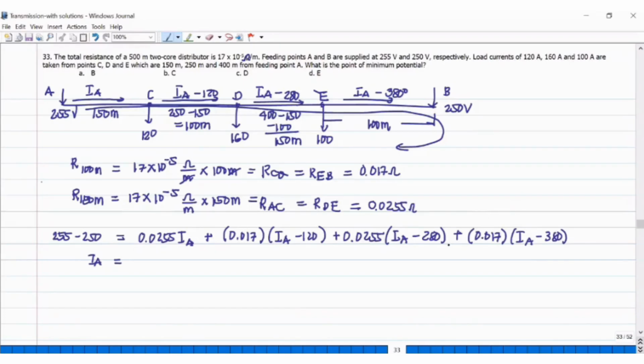So the value of IA, according to my calculation, is 242.824. Then the voltage at C is 255 minus the drop here, 150 meters, so 0.0255 times IA, 242.824. What I computed for VC is 248.808 volts.